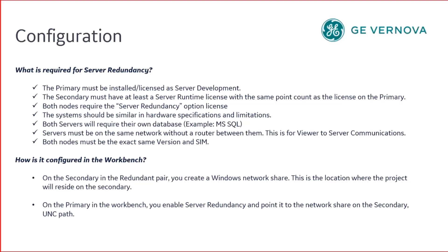How is it configured in the Cimplicity workbench? On the secondary in the redundant pair, you create a Windows network share. This is the location where the project will reside on the secondary. On the primary in the workbench, you enable server redundancy and point it to the network share on the secondary via UNC path.